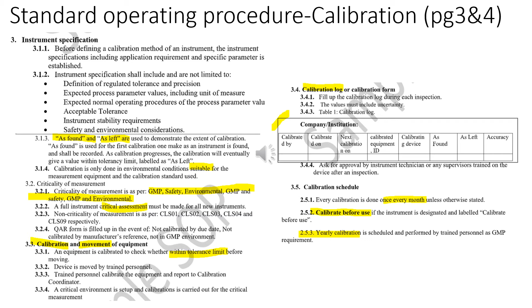So it is part of the GMP requirement, and there is a need to adhere to the critical assessment. The critical assessment is as per point 3.2, and everything is kept within the tolerance limit and the criticality is found out. During calibration, it is important to find out the as found and as left to show that the instrument is well calibrated and the accuracy is also defined. And it should be done regularly, every month and every year.